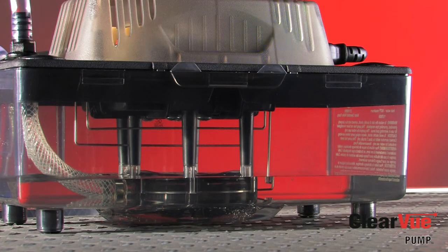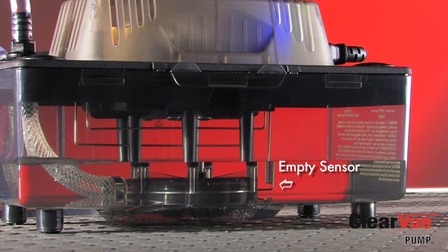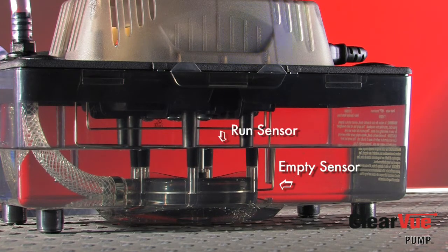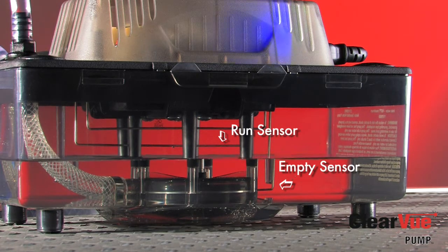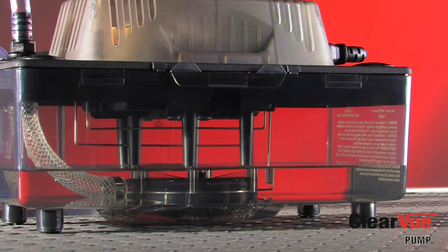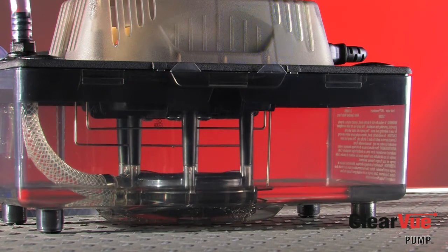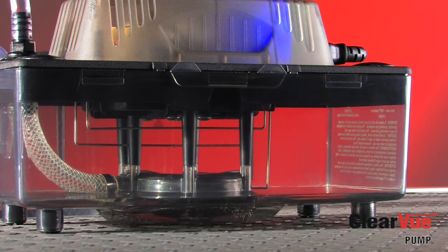As you can see, water is coming into the tank and it's touching that empty sensor — the bottom sensor. This sensor lets ClearVue know that there's water in the tank. Water will continue to rise until it touches the run sensor. The run sensor uses what we call our IQ technology, which are the brains behind the pump. These brains determine how fast to run the motor to remove the condensate. So ClearVue will slowly ramp up the pump speed, which gives you the quiet operation as compared to full throttle mode.